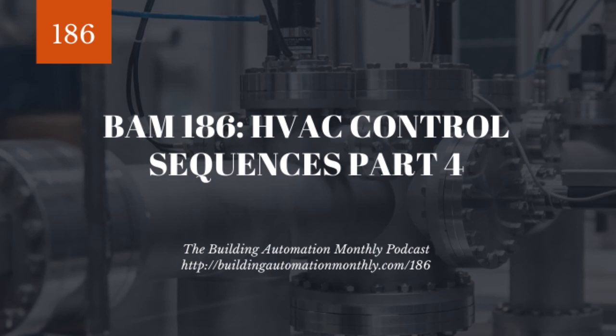Makeup air units, they have a lot of different things going for them, right? You can have just pure makeup air units with just a fan and an outdoor air damper, and it's bringing in air at a static CFM value, and that is balanced so that it pressurizes the building. Then on the complete flip side, you have makeup air units which are variable, which have mixed air returns, which have face and bypass dampers, which is something we haven't really talked about here yet. So let's start to unpack the most complicated, and then we'll go from there.